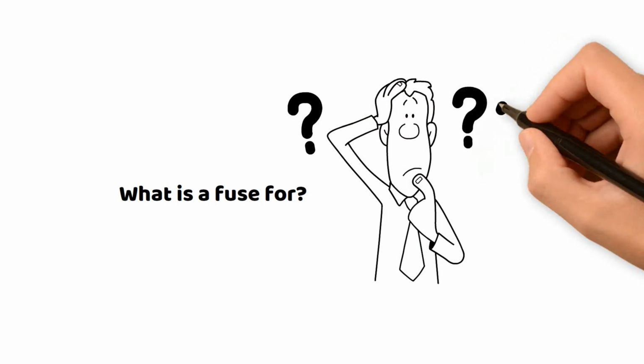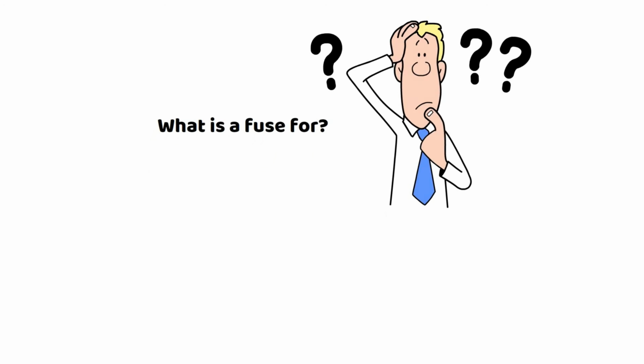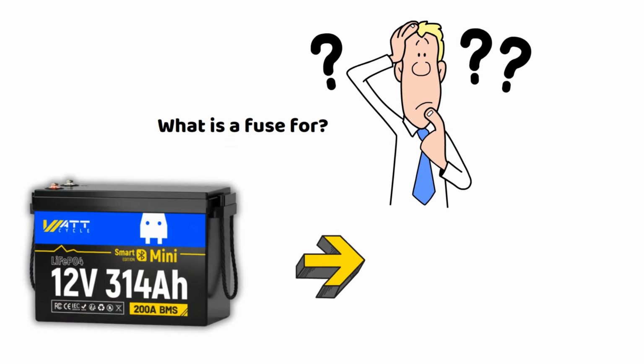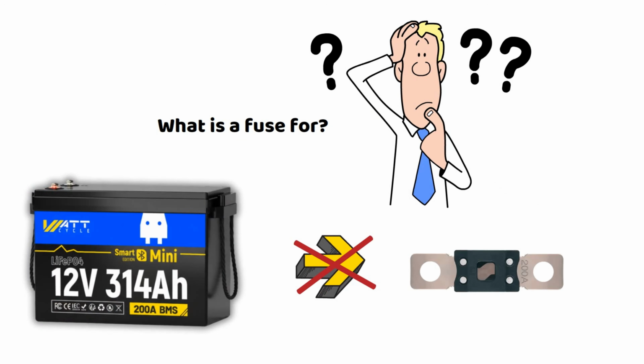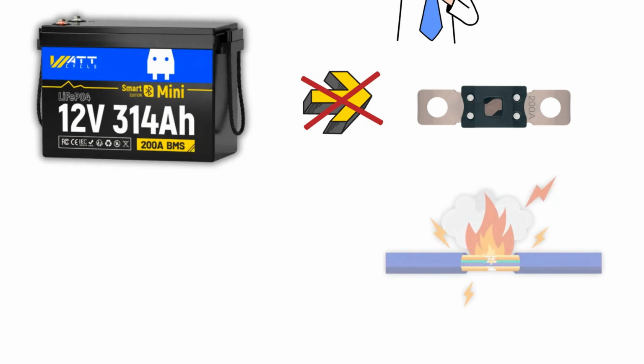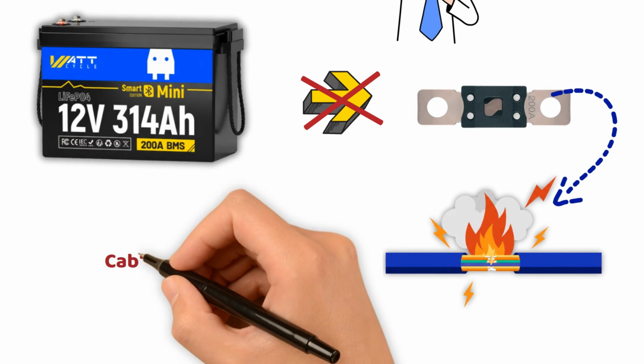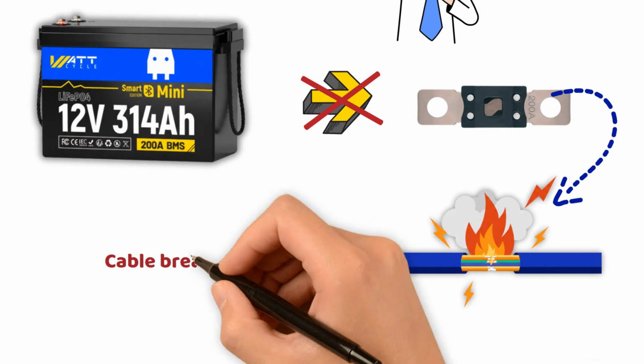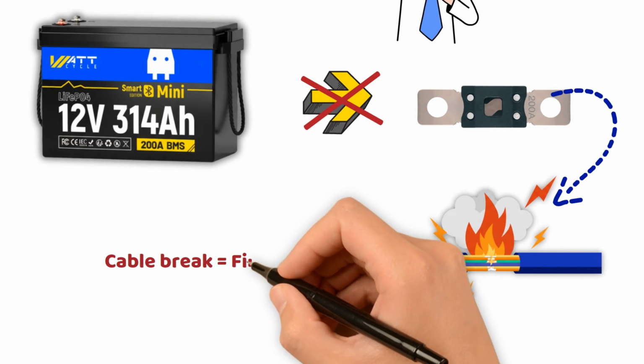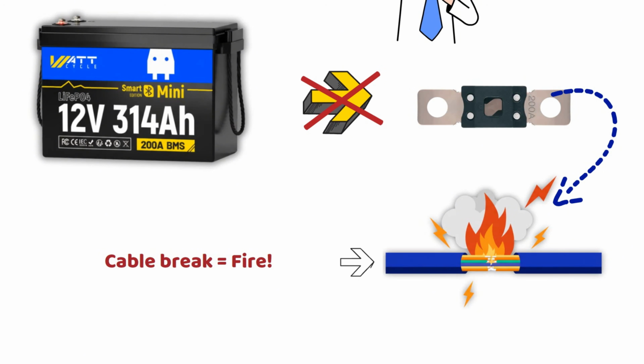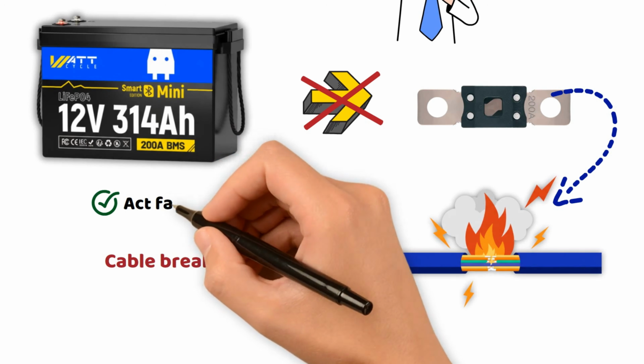Let's start with a basic question. What is the purpose of a fuse? Contrary to popular belief, the fuse is not there to protect your battery, but rather to protect your cable. Its role is critical. It must blow and interrupt the circuit before the cable overheats, melts the insulation, and starts a fire. It must be able to act quickly in the event of a short circuit, especially with lithium batteries, which can instantly release enormous currents compared to a lead-acid battery.